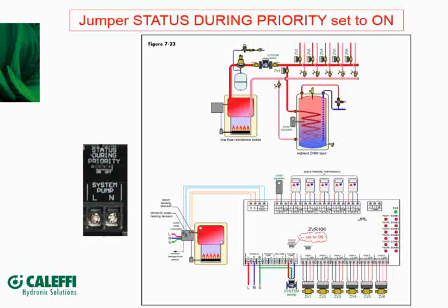Yeah, and I think someone just asked a question about the exercise on the zone relay. Obviously, you can't exercise that pump if the valves are closed. That's the key there, right? Well, actually, it does. We spoke to the pump manufacturers on that, and they said that the 30 seconds of on time would be fine with their pumps every 72 hours even. Regardless of what type of pump, even a high head pump or something? Well, that's what they're telling me because it's such a short span of time. And I know even with the Alpha and stuff like that, the Alpha probably takes like 15 seconds before it actually gets done with its initiation. But yeah, I'm told it would be fine with that.